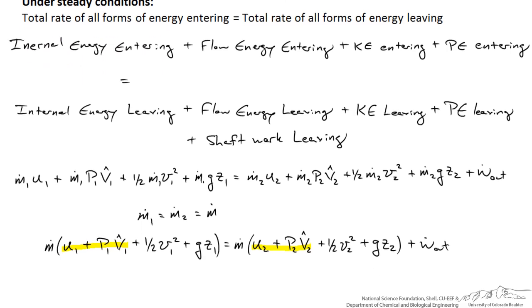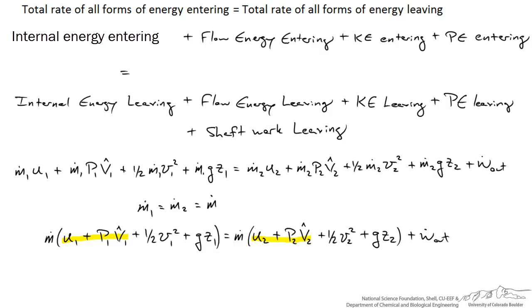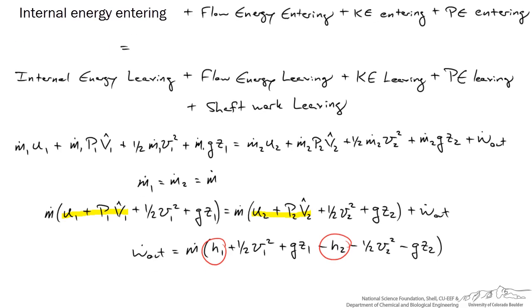So I'm going to solve for W out now and make that substitution for h. An assumption we can often make is that these terms h1 and h2 are usually fairly large compared to the kinetic and potential energy differences. They're so large in fact that it may only make a percent or two difference. If we're trying to calculate W out, we might get by by just saying W out equals the mass flow rate through the turbine times the enthalpy of the stream entering minus h2.